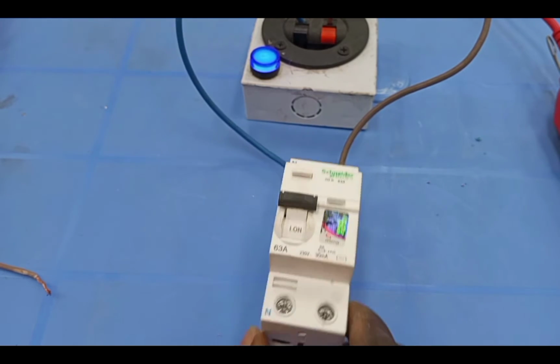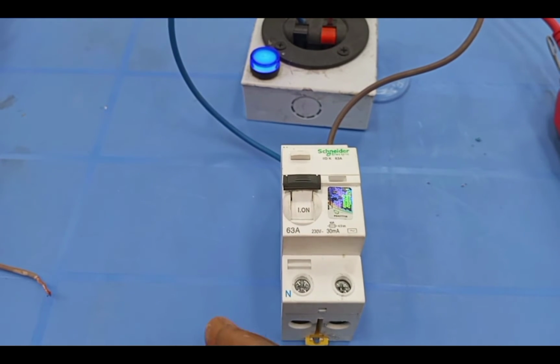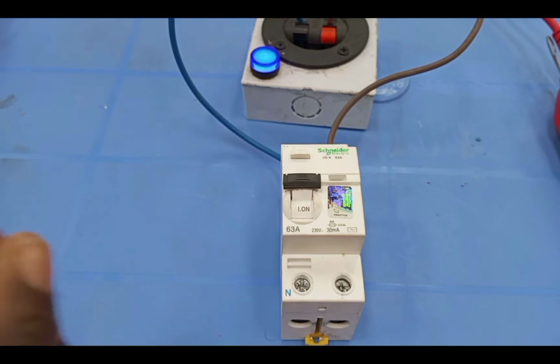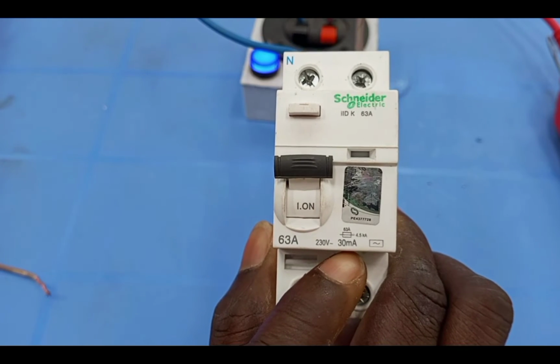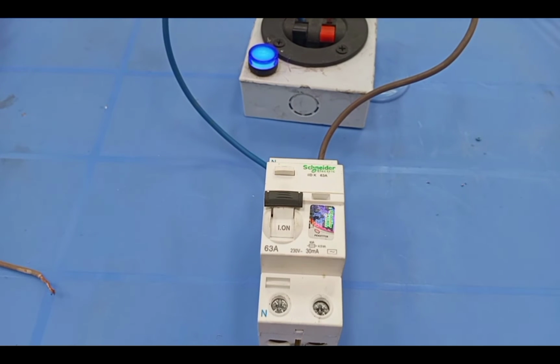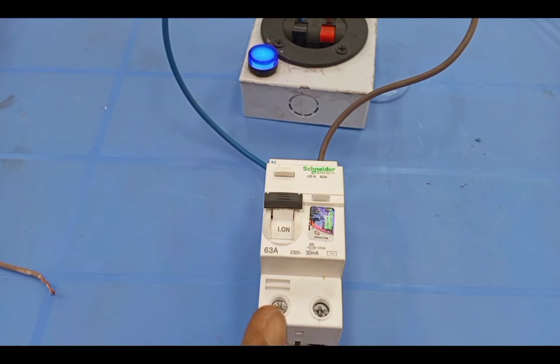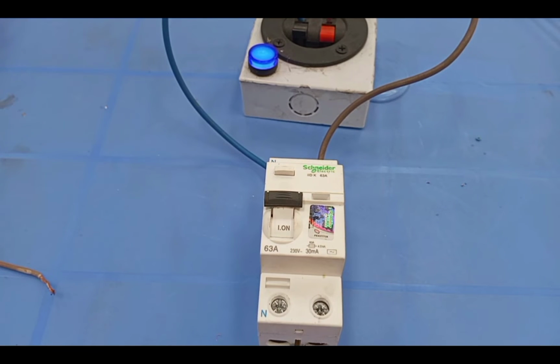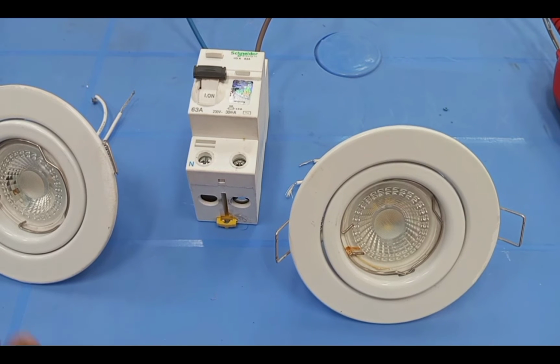If we are employing RCD in our circuit, what we should be mindful of mostly is the 30 milliamp here. This is because there is not only one rating for RCDs. Depending on where you are using them, we have 30 milliamp rating, we have 100 milliamp rating, we have 300 milliamp rating. If you are selecting an RCD to protect human beings, then the best rating you should get should be 30 milliamp and below. All right, so now I'm going to demonstrate to you how the RCD works.